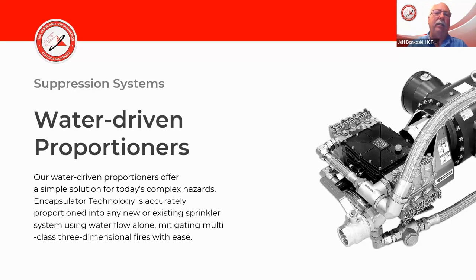When we start looking at these water-driven proportioners, they don't require any electricity. They work based on water flow. Think of it like the hamster wheel. The faster the water flows, the more it increases the speed of the pump, and it puts more of the concentrate into the water stream. It works over a wider range of flows. It might work from 200 gallons per minute up to 1,200 gallons a minute.